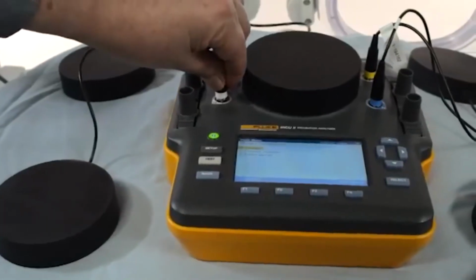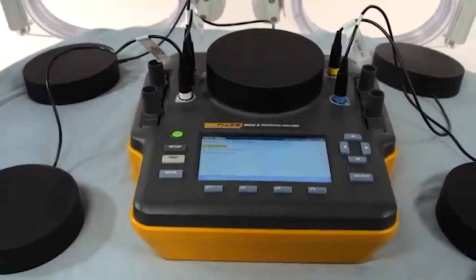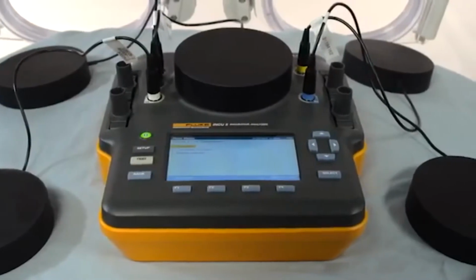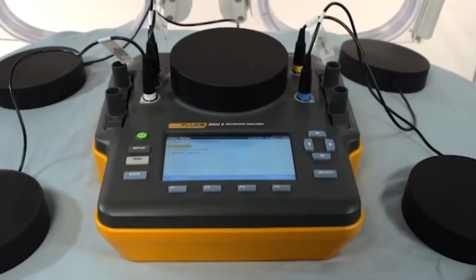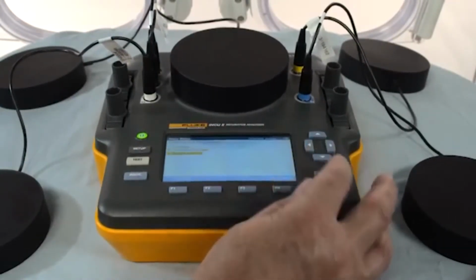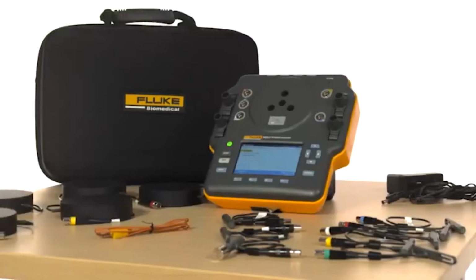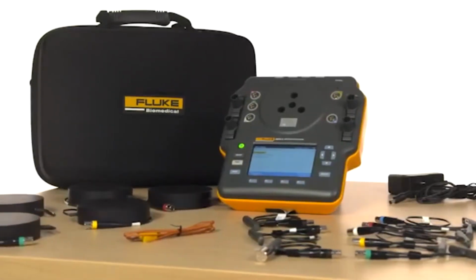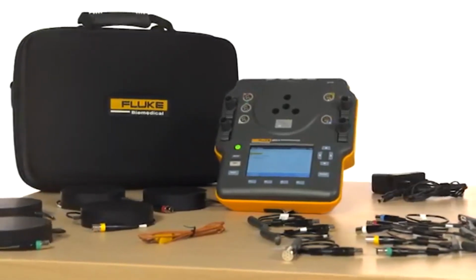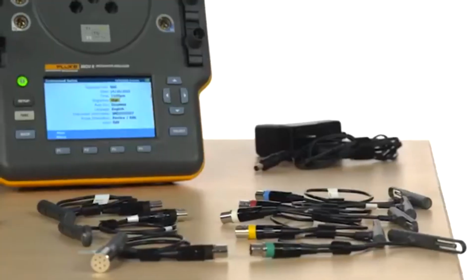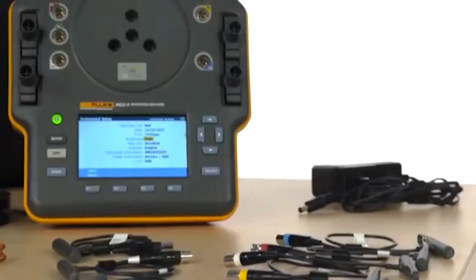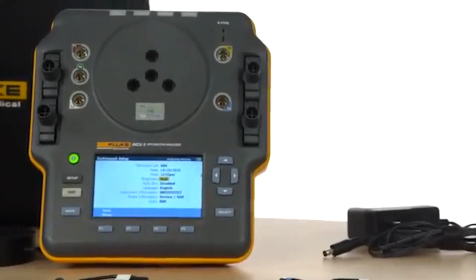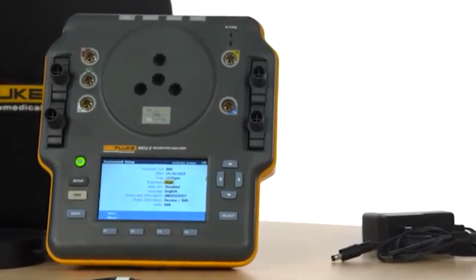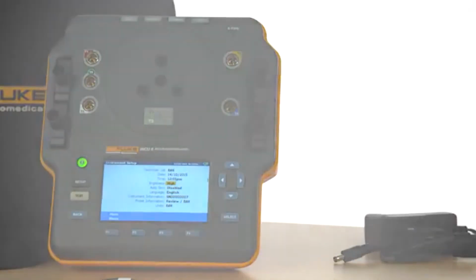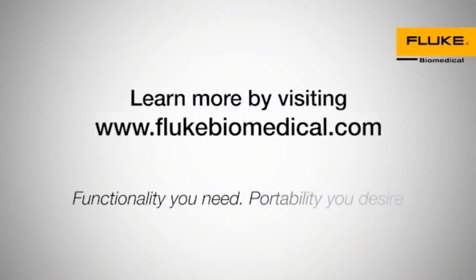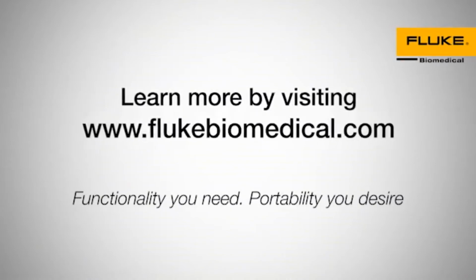To test radiant warmers, simply replace the temperature probes with the radiant pucks. Position them around the warmer according to the standard. Select the appropriate test and testing environment. We've designed the INCU2 to not only be highly portable and easy to use, but give our customers a best-in-class all-in-one solution. The INCU2 is compliant with all global IEC standards for radiant warmers, incubators, and transport incubators. Learn more about the INCU2 by visiting flukebiomedical.com.